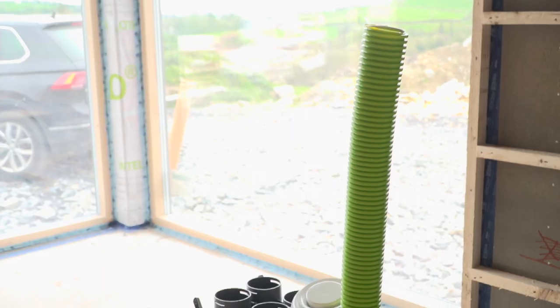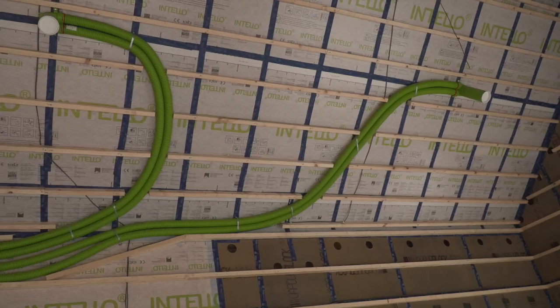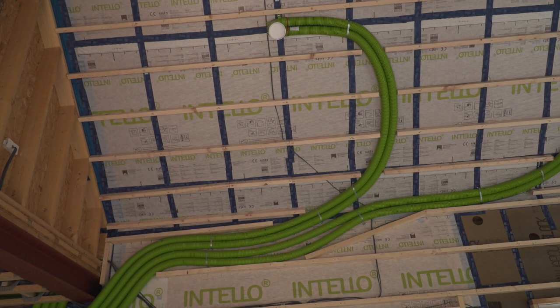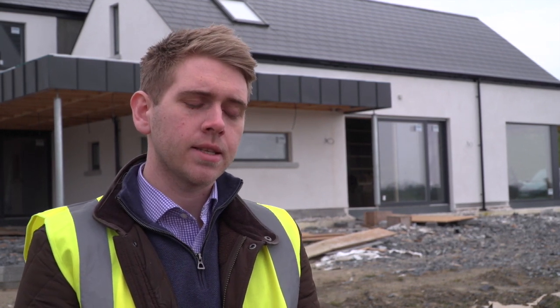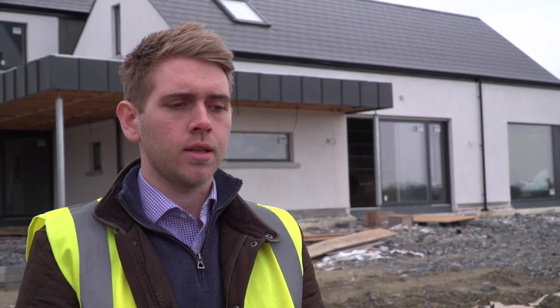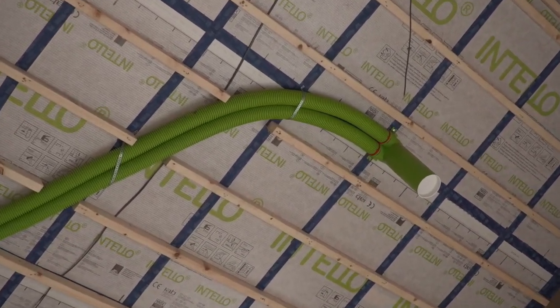The MVHR system in Nile's house is a Brink Renovant Excellent 450 machine, installed with the Ubbink Air Excellent ducting system. The two systems are from sister companies that work together to create the MVHR system. The 450 refers to the metres cubed per hour the machine can do. Upon sizing the house we estimated it would require roughly 220 metres cubed of air, so we put in the 450 machine, which allows the unit to run at roughly 50% of its maximum capacity, while still being able to ramp up to a much higher level should it need to.